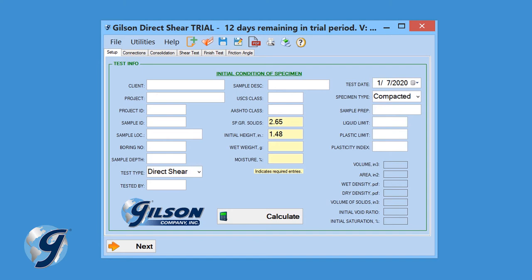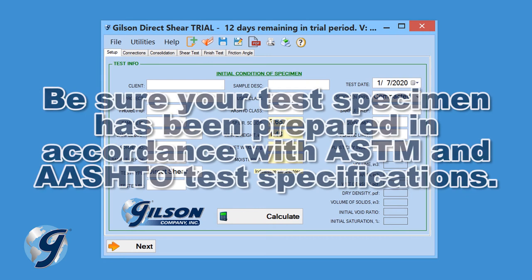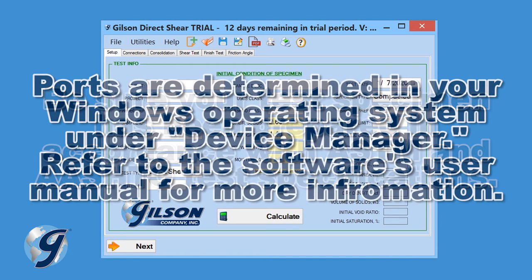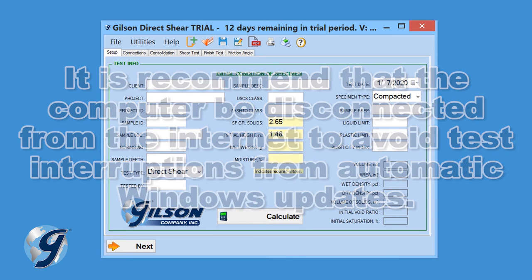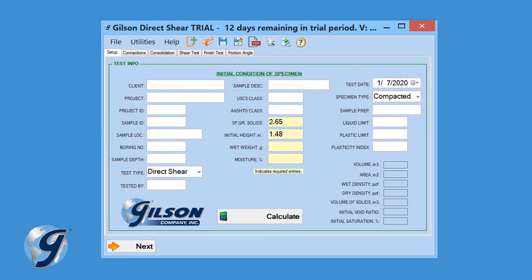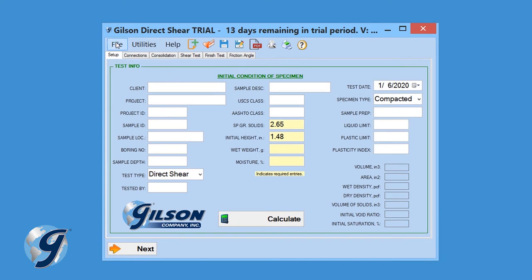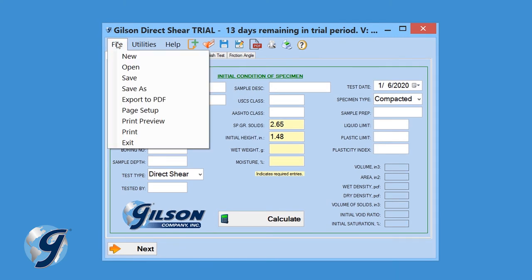Now that we have reviewed the menu bar, let's demonstrate how to perform a new test using the Gilson HMA-610 Direct Residual Shear Data Acquisition Software. Make sure all connections to the computer and the data readout box are secure. It is recommended that the unit be disconnected from the internet to avoid test interruptions from automatic Windows updates. Click on File and New to begin the process.